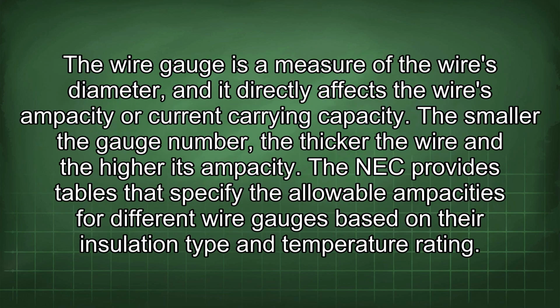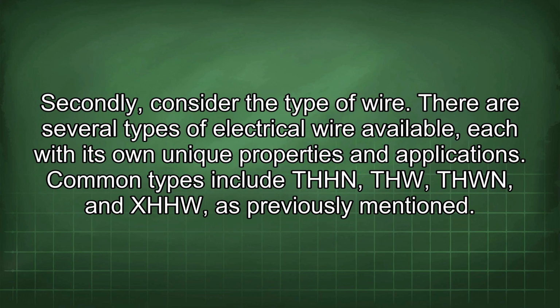The wire gauge is a measure of the wire's diameter, and it directly affects the wire's ampacity, or current carrying capacity. The smaller the gauge number, the thicker the wire, and the higher its ampacity. The NEC provides tables that specify the allowable ampacities for different wire gauges based on their insulation type and temperature rating. Secondly, consider the type of wire.